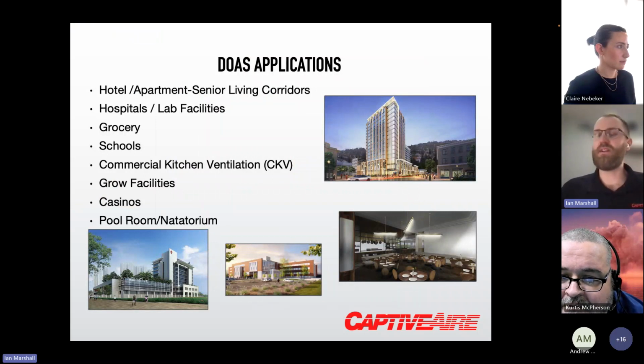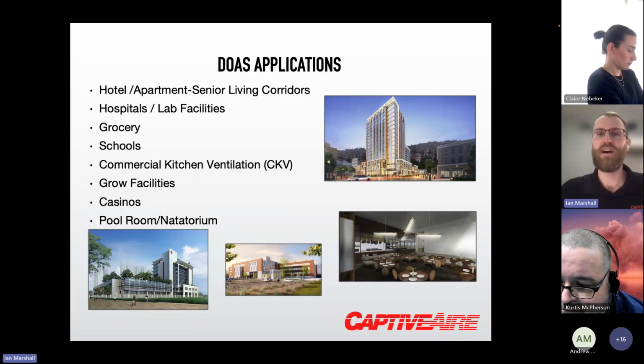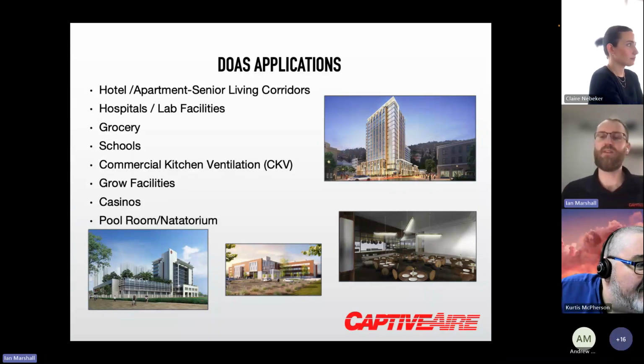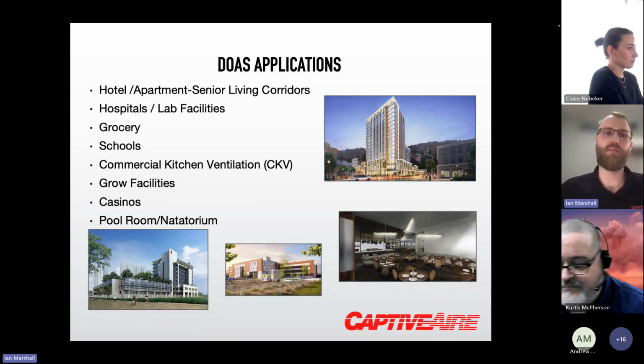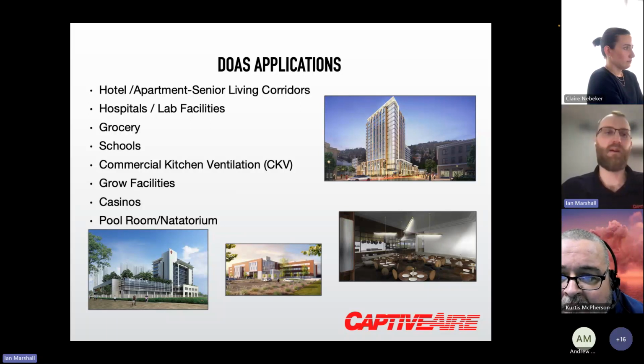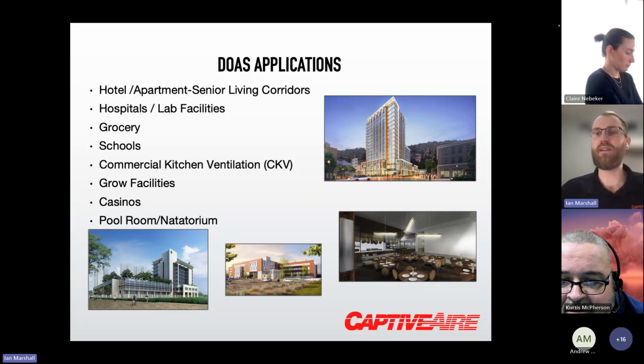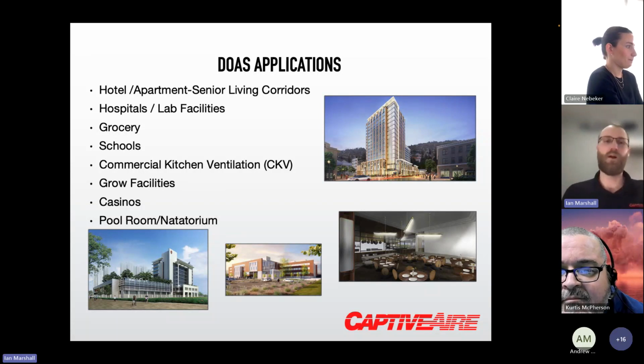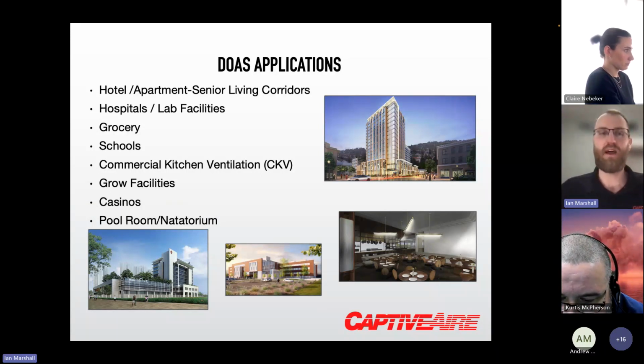So for applications, we really get involved in a wide variety of things. This is just a small list of what we see, but a very common or popular DOAS application would be hotel corridor pressurization, or apartment or senior living, where we're pressurizing the corridors and bringing in the ventilation that way, and then each individual guest room or hotel room has its own individual heating cooling unit. So again, a space that requires a high volume of ventilation. We get involved a lot with hospitals and labs, where they need high volumes of ventilation, and in many cases very tight and precise temperature and humidity control, which is what the DOAS has the capability of doing. Grocery applications require pretty low dew points. Schools obviously are heavy on the ventilation side. Kitchen ventilation, again, something that CaptiveAire is familiar with, but it's a small portion of the jobs that we get involved with this product line.